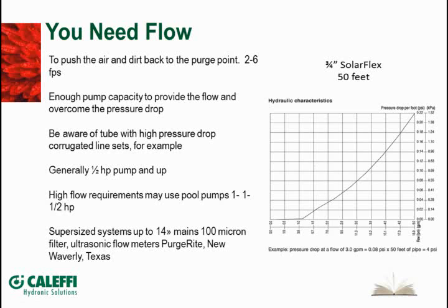It's a tough one to get air out of sometimes if you don't have enough pump, and also with all those little ridges and stuff in there, it tends to trap air. So the only solution there is to have enough flow going through that to be able to push that air out of it.